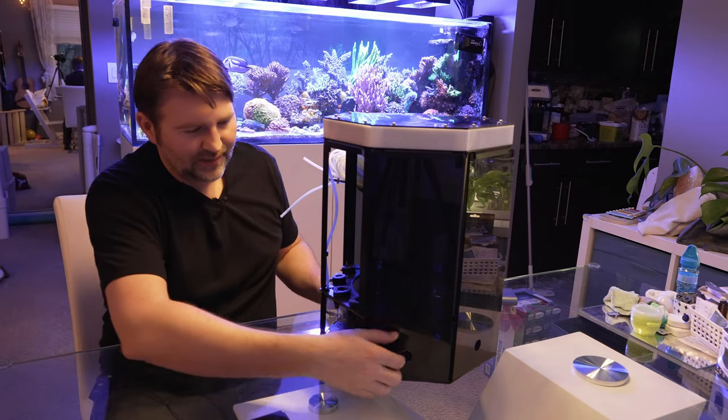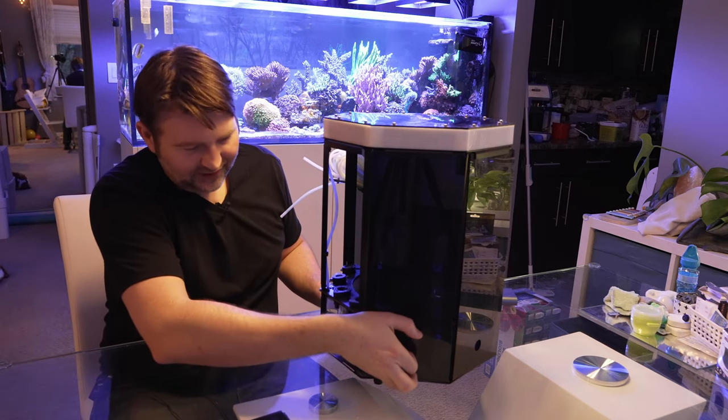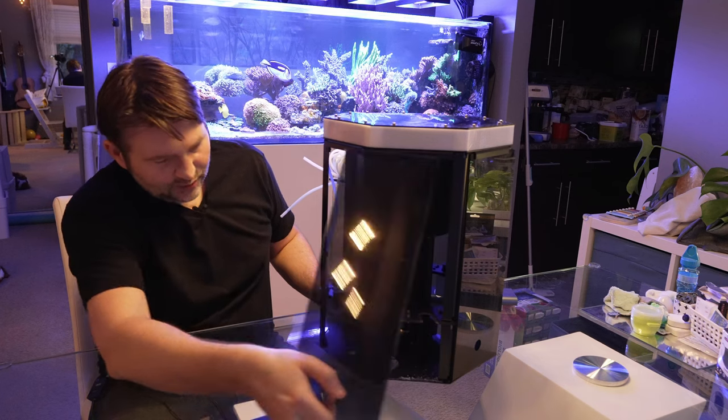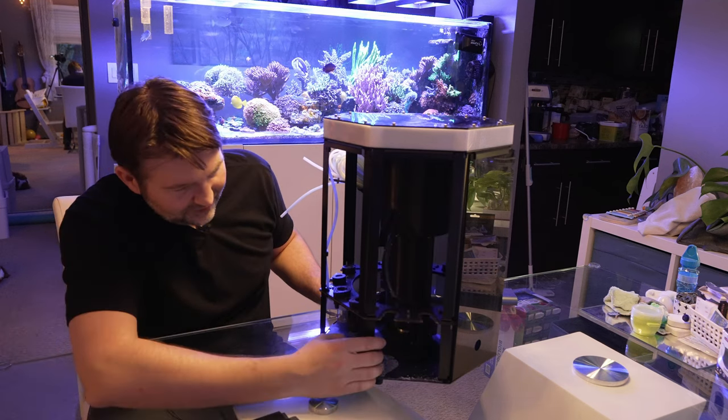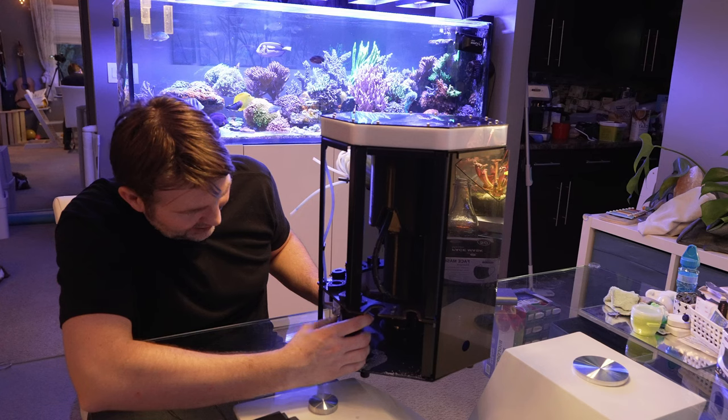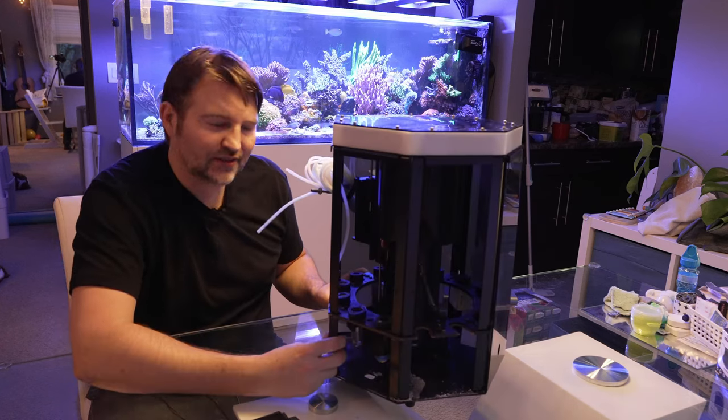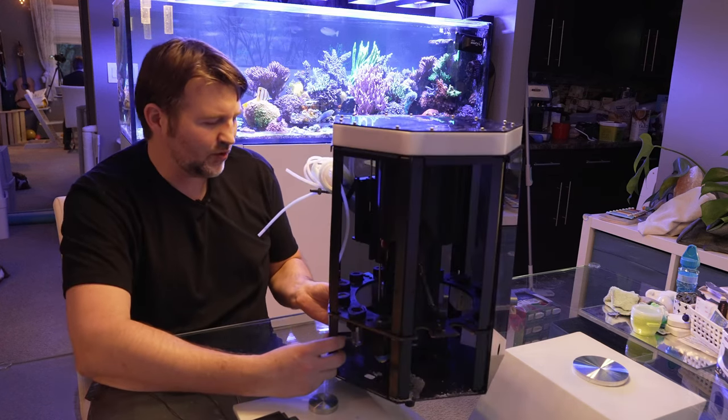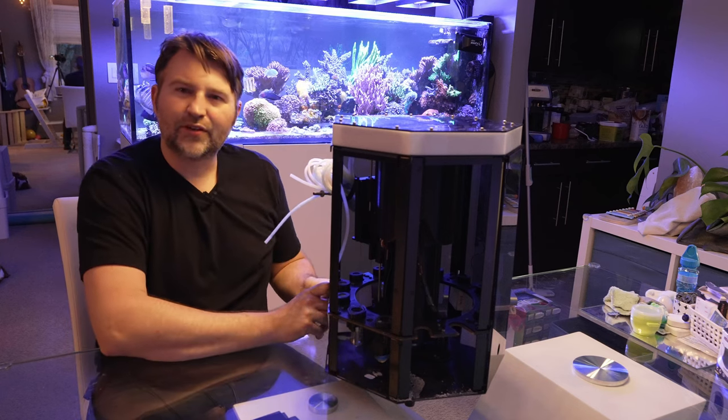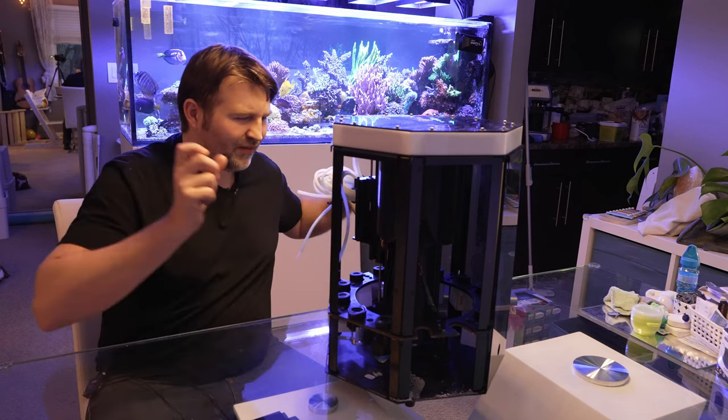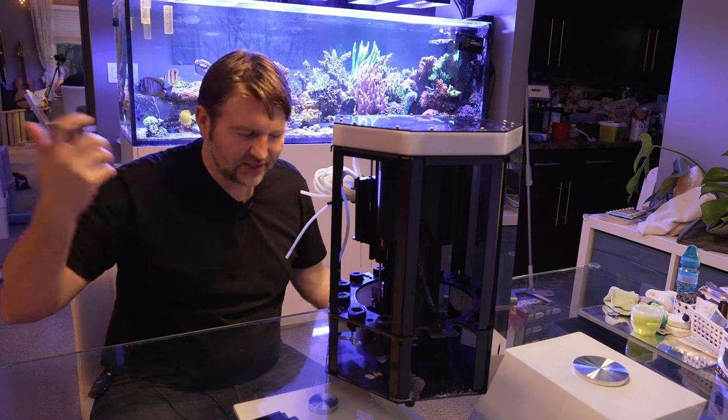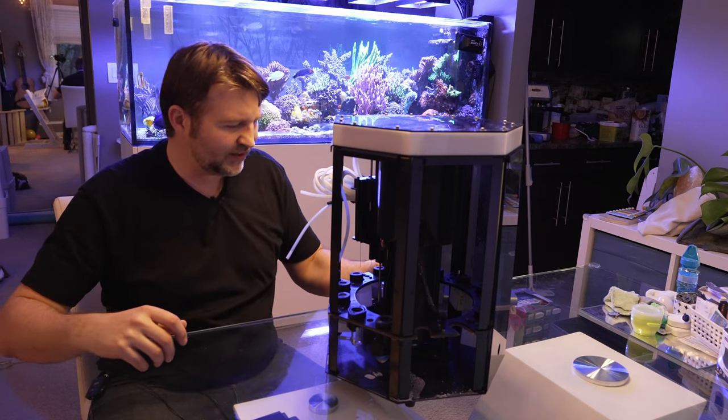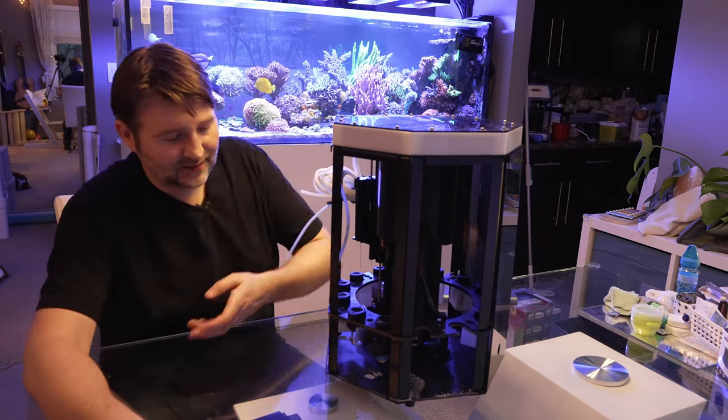Now over the years, it's been about a year and a half now that I've been running this and it has worked very well for me. The only issue I had is I did have a leak at one point in the reaction chamber and it was just due to the tubing starting to corrode a little bit from the corrosiveness of the reagents. So there's about five mil or so that had a little bit of a split so I just cut off the tube, reattached it, back in business. Overall it was fairly minor and easy to fix.